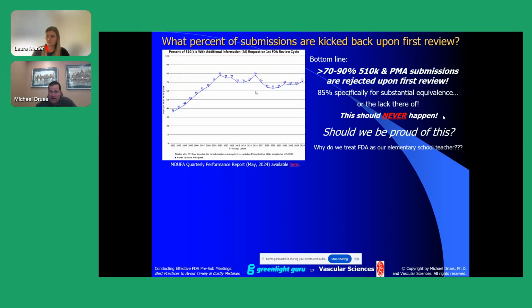This should never, ever happen. Can I be any more clear than that? This should absolutely not happen. Once again, it's an amateur mistake. It's an elementary school mistake. It's a boneheaded mistake. This risk can be greatly mitigated, if not completely avoided, by taking your device to the FDA in advance of your submission, i.e. using a pre-sub to, among other things, talk about your regulatory strategy. If it's a 510K, here's the predicate that we're going to use. Here's the product code that we're going to use and all of the reasons why.